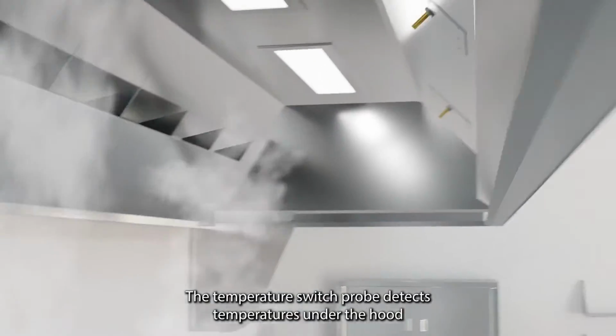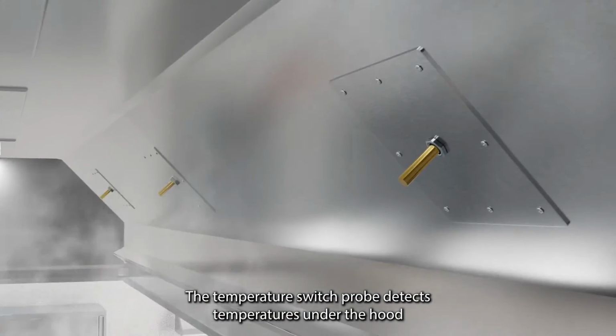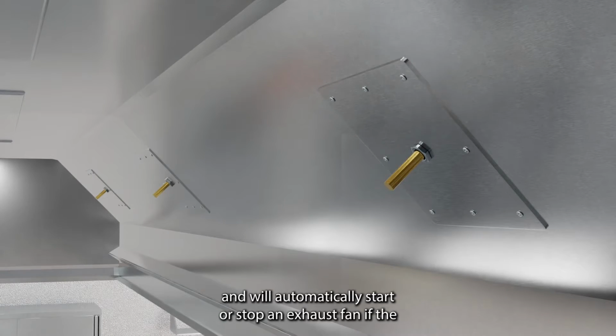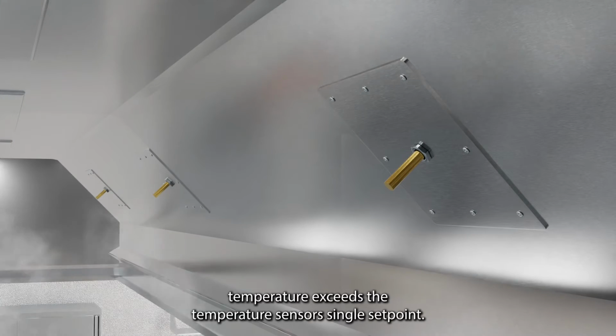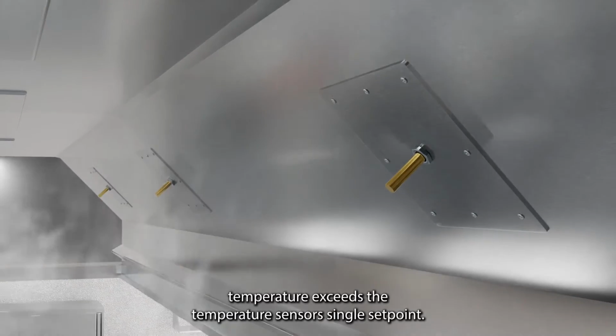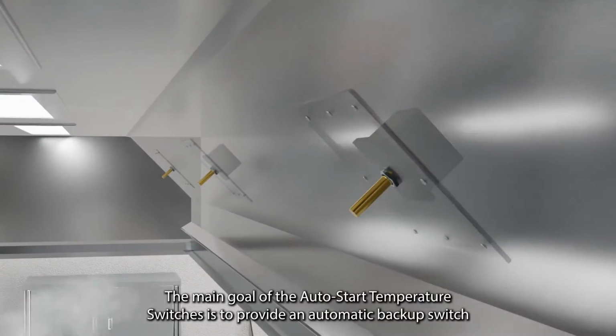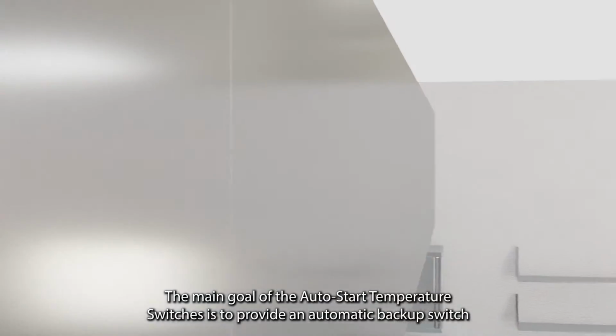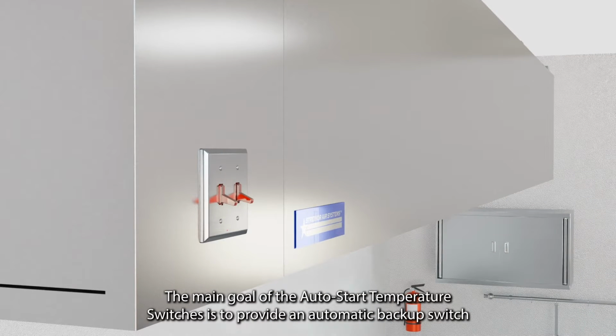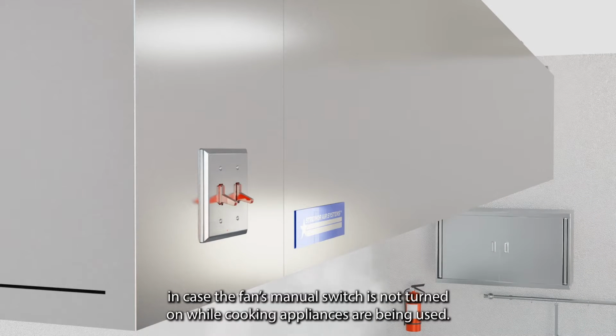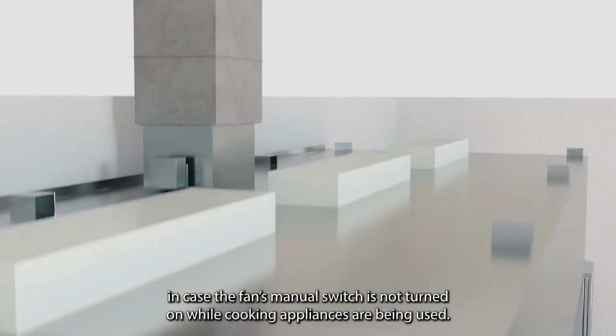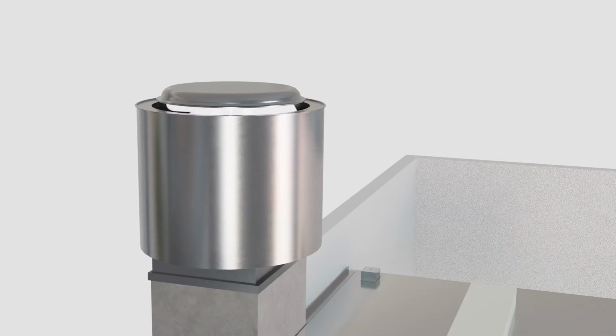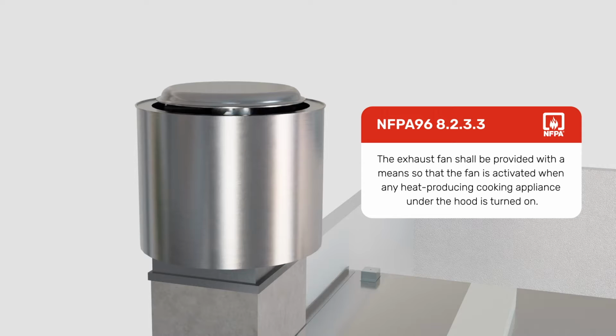The temperature switch probe detects temperatures under the hood and will automatically start or stop an exhaust fan if the temperature exceeds the temperature switch single set point. The main goal of the Auto Start temperature switch is to provide an automatic backup switch in case the fan's manual switch is not turned on while cooking appliances are being used. This is important because the prevailing NFPA 96 code requires that an exhaust fan be able to automatically activate when any heat-producing cooking appliance under the hood is turned on.